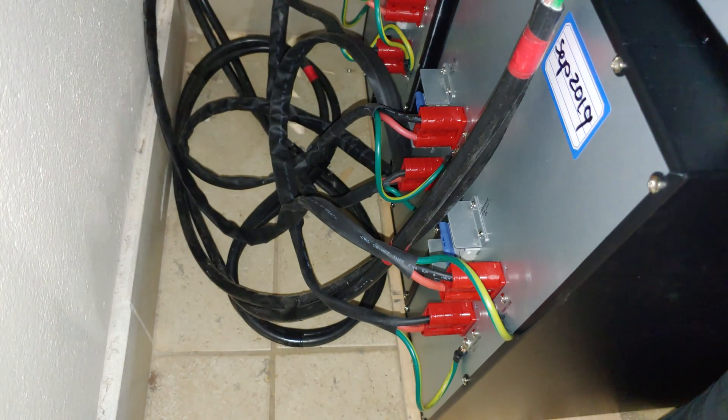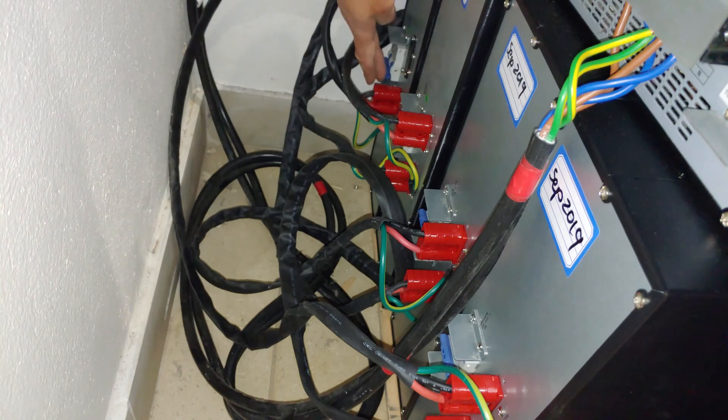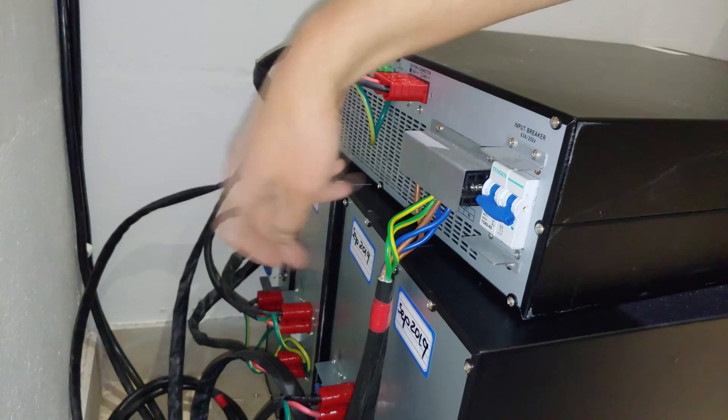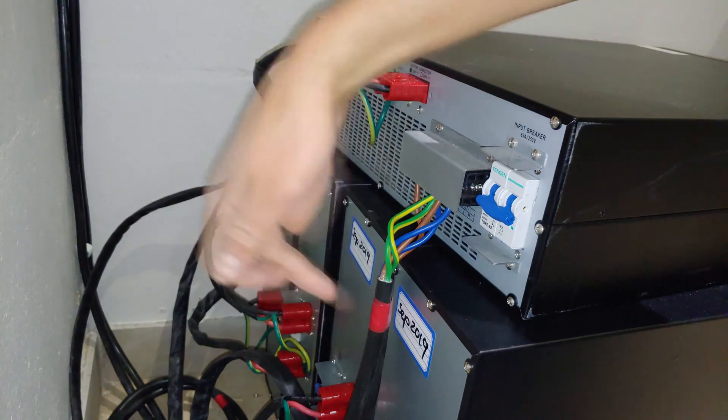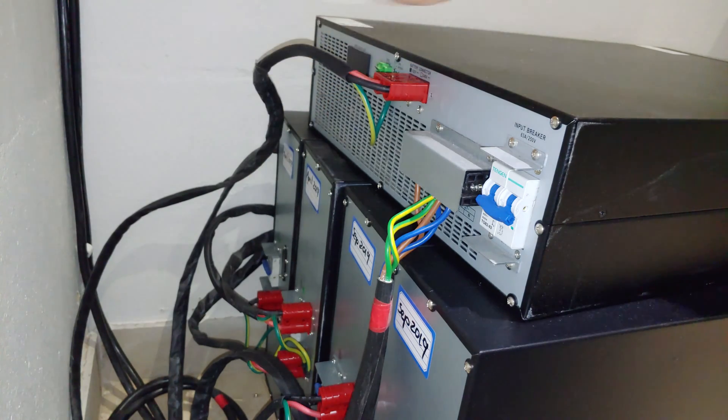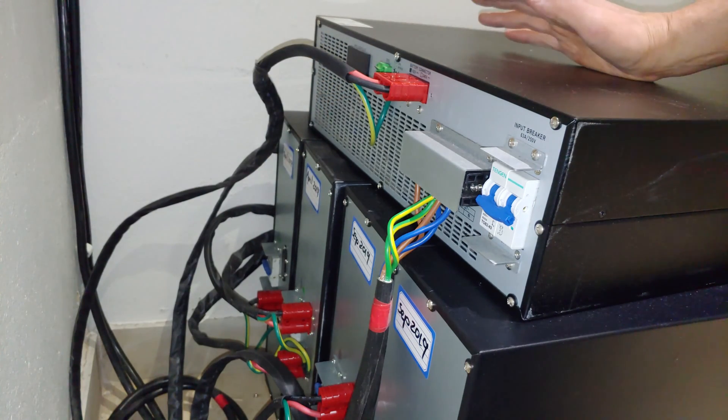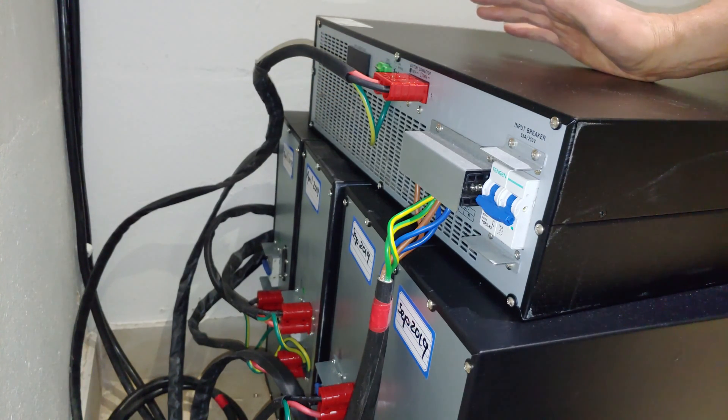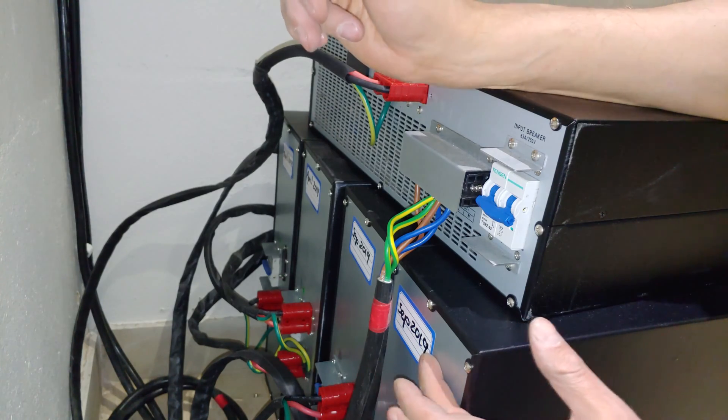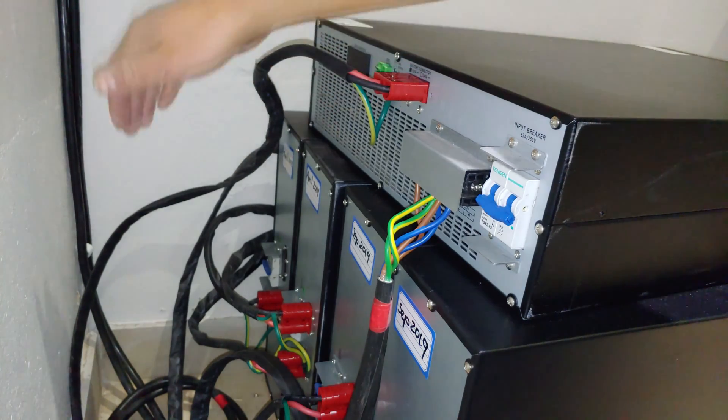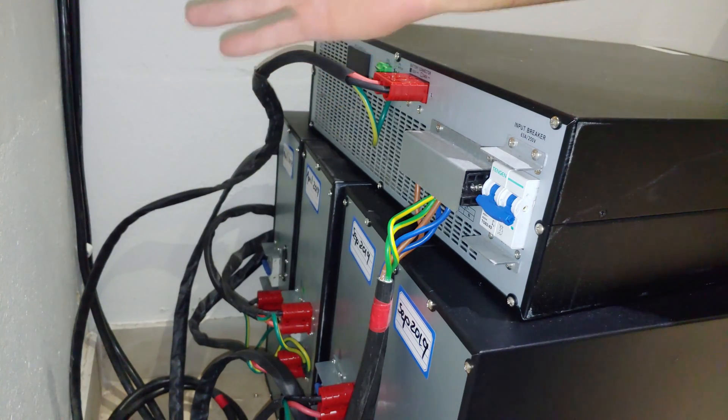Now the next thing you do is you'll just turn them all on: one, two, three, and four. So now they're all on. Lastly, it's very important to date your battery banks because these battery banks obviously have a lifespan. Lead acid batteries just decay over time, so I just put the date—these were April, these are September, for example.